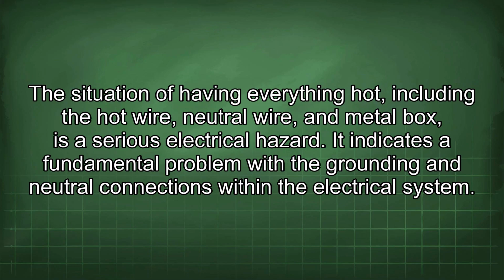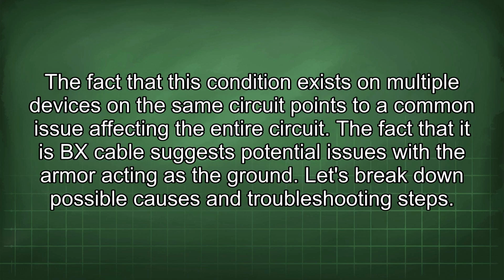The situation of having everything hot, including the hot wire, neutral wire, and metal box, is a serious electrical hazard. It indicates a fundamental problem with the grounding and neutral connections within the electrical system. The fact that this condition exists on multiple devices in the same circuit points to a common issue affecting the entire circuit. The fact that it is BX cable suggests potential issues with the armor acting as the ground. Let's break down possible causes and troubleshooting steps.